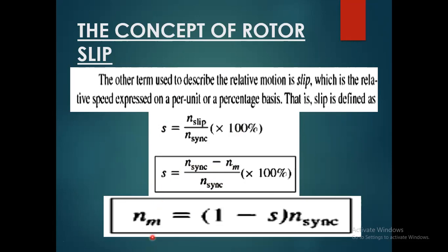And if we know the value of slip and the synchronous speed and want to find the motor mechanical speed, we use this formula: 1 minus s, multiplied by the synchronous speed. By this formula, we get the value of the rotor speed.